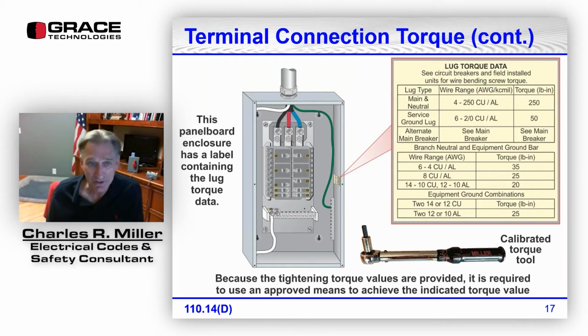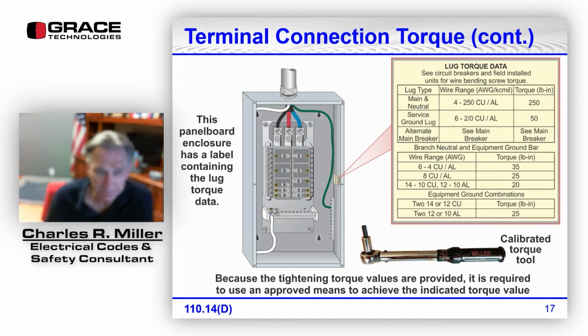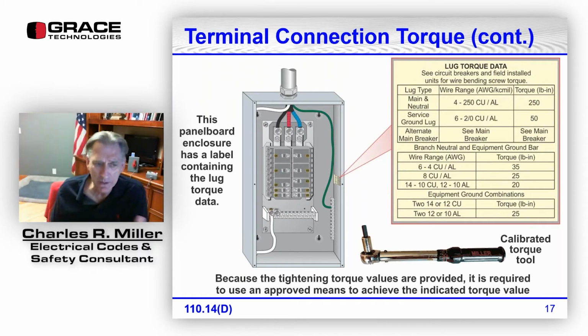All right, so we have the lug torque data that's on the panel board. Because the tightening torque values are provided, it is required to use an approved means to achieve the indicated torque value. And this is a torque socket wrench. It is the Miller brand torque socket wrench.